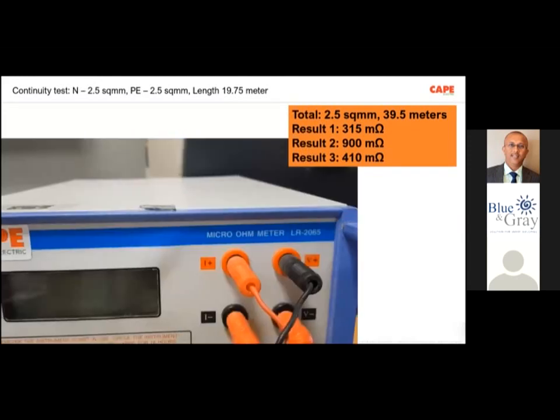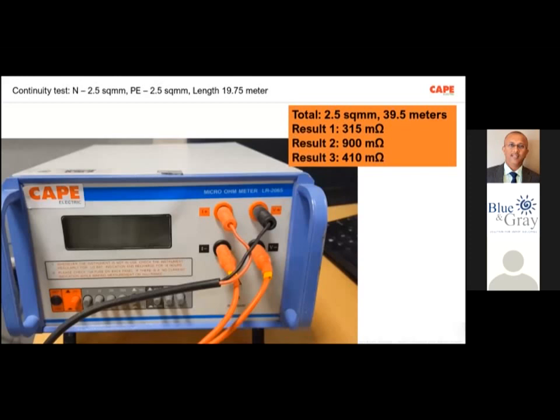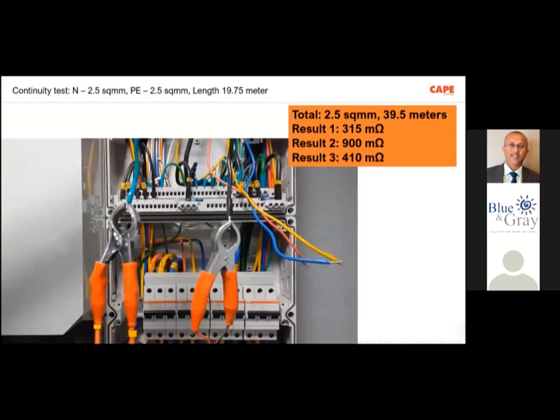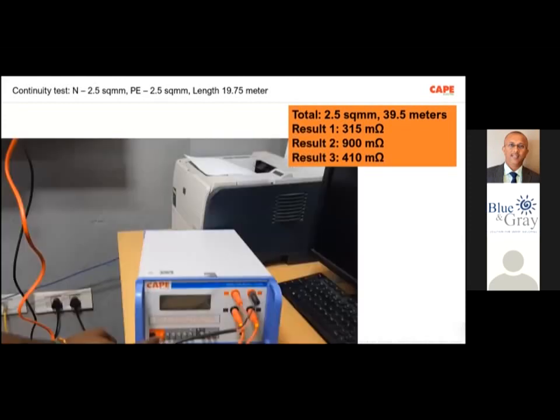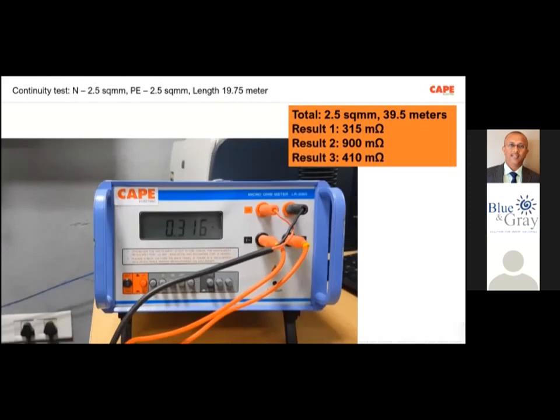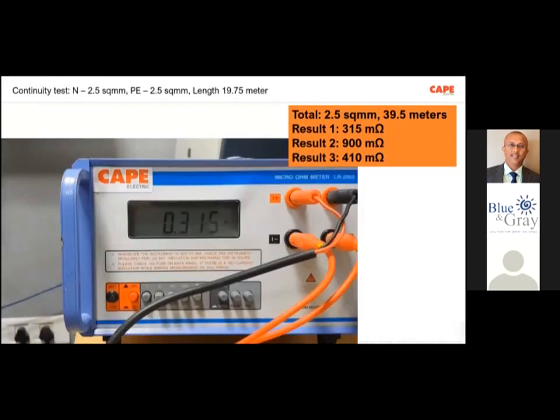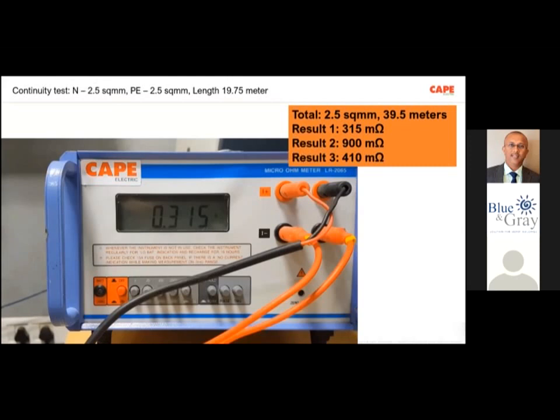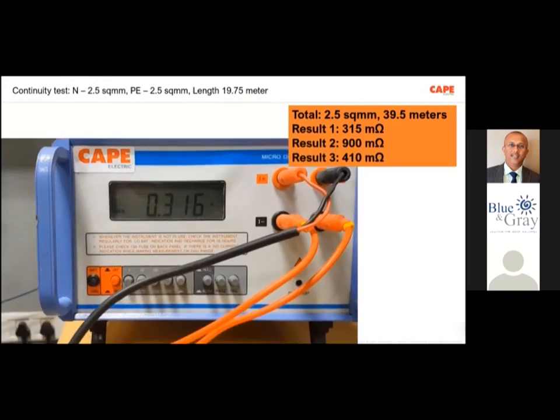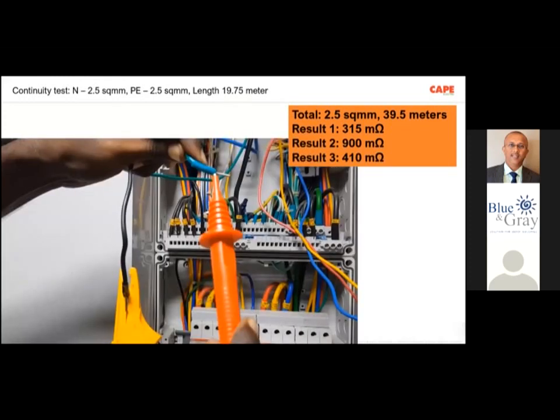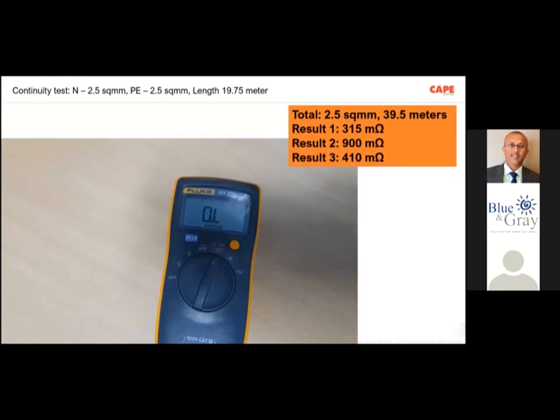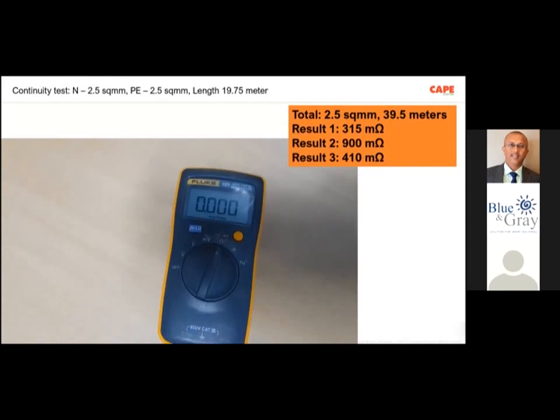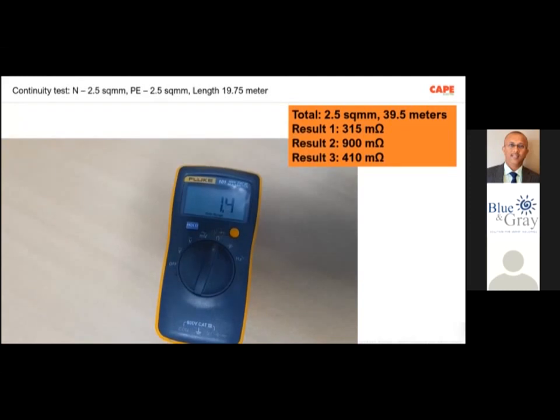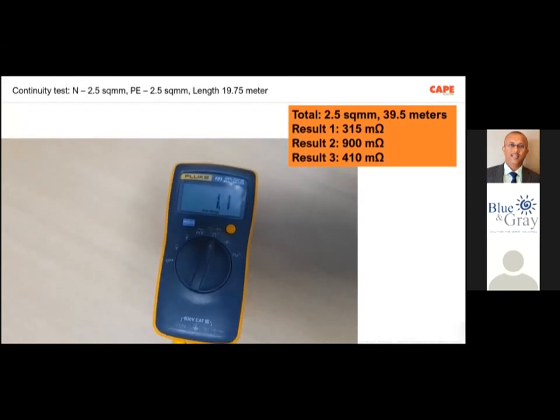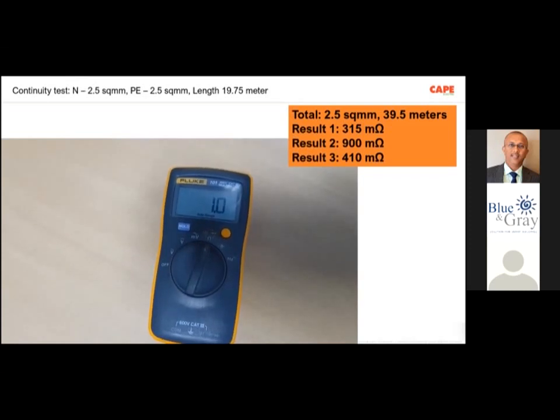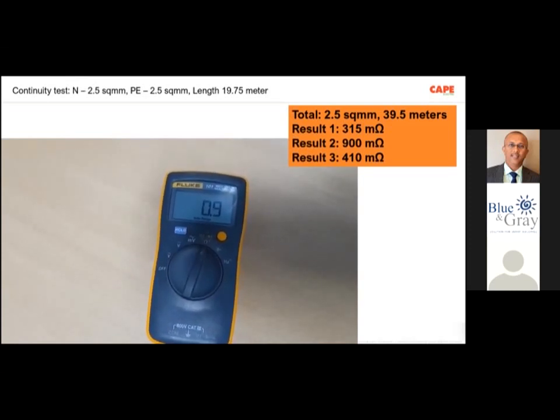Then on the distribution board we do the testing with a micro-ohmmeter. In a 4-pole test with a micro-ohmmeter, the continuity resistance is measured, and it is approximately 315 or 316 milliohm. Then the same test, just for your information, is carried out with a normal multimeter. In a normal multimeter, you get the value as 900 milliohm. See, 900 milliohm, this is the final value.